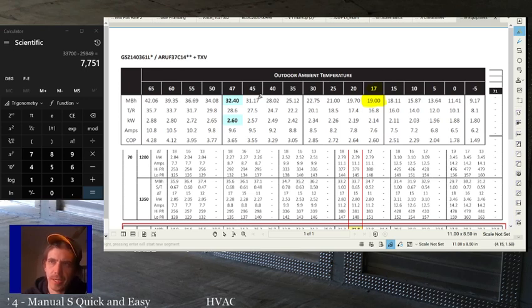The other thing is to determine where it drops off. So if you know your load at these different temperatures, which if you're using software, it's not that hard to find, you can determine how many BTUs of electric heat you need at these different temperatures, and again, you would use that to lock out the heat when it's too warm outside to need to use electric heat.